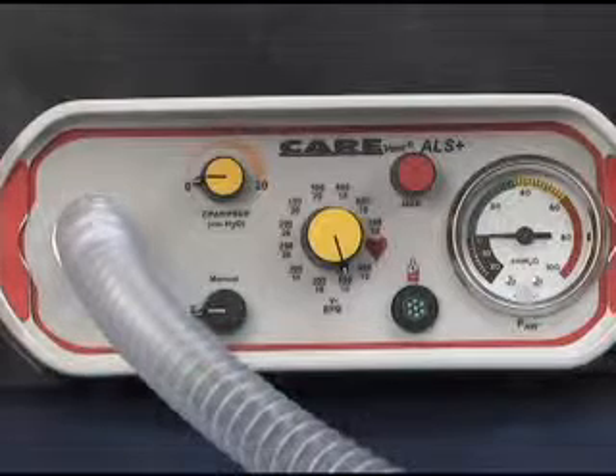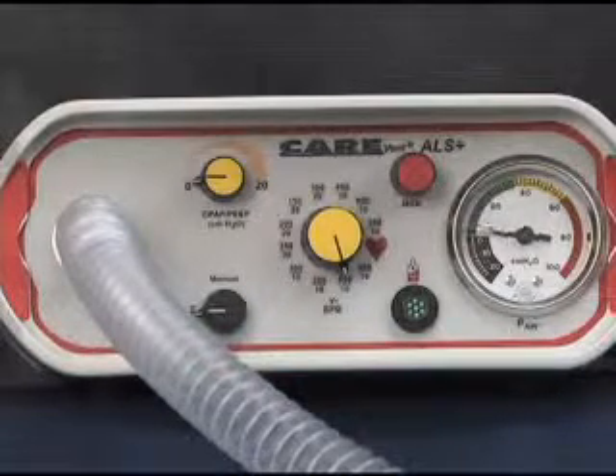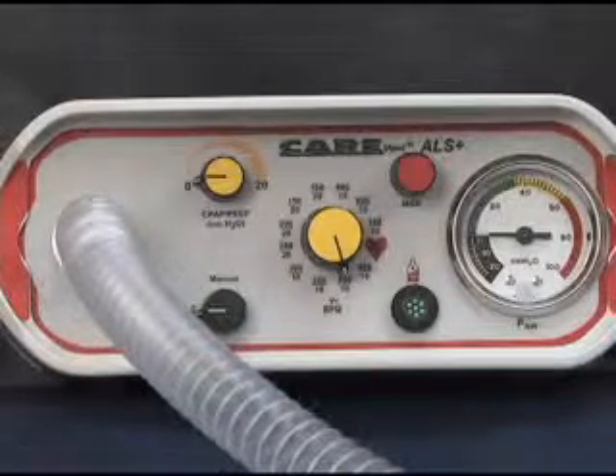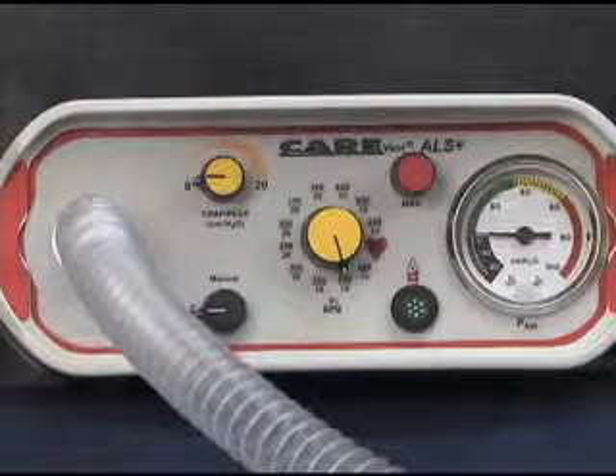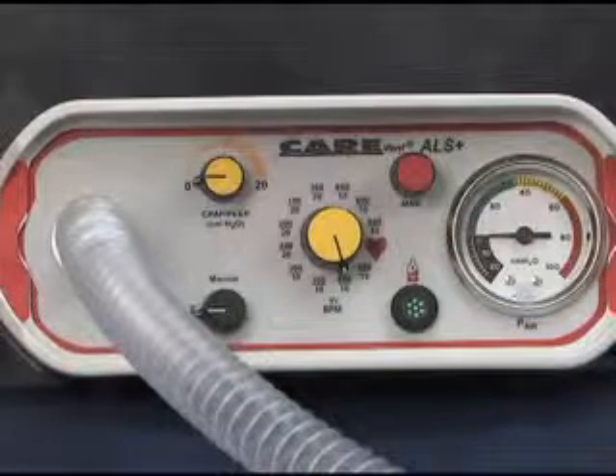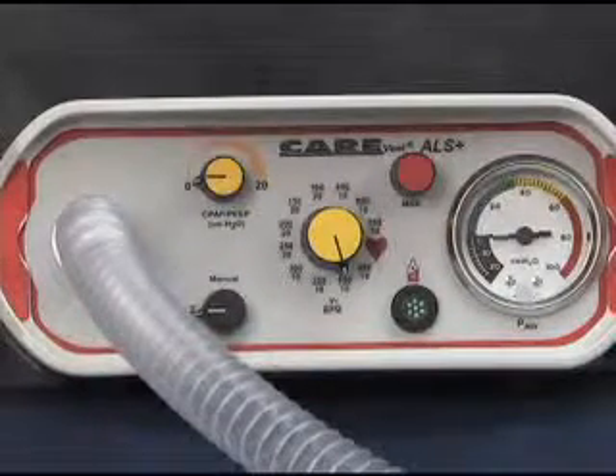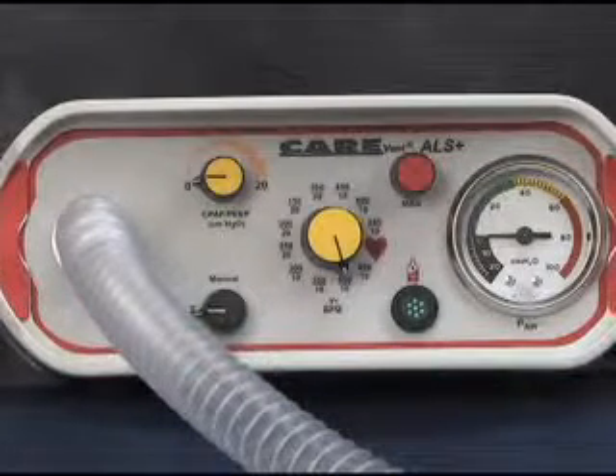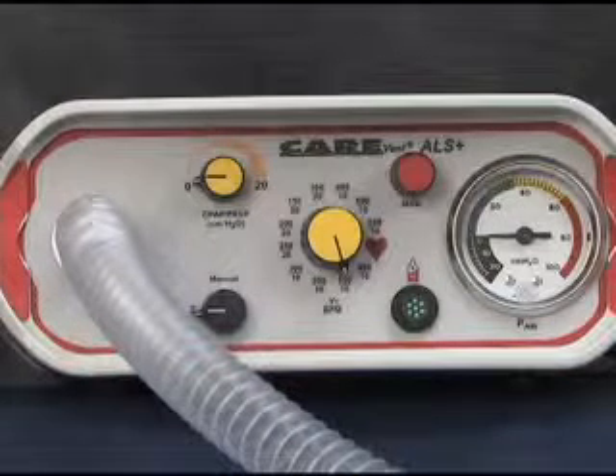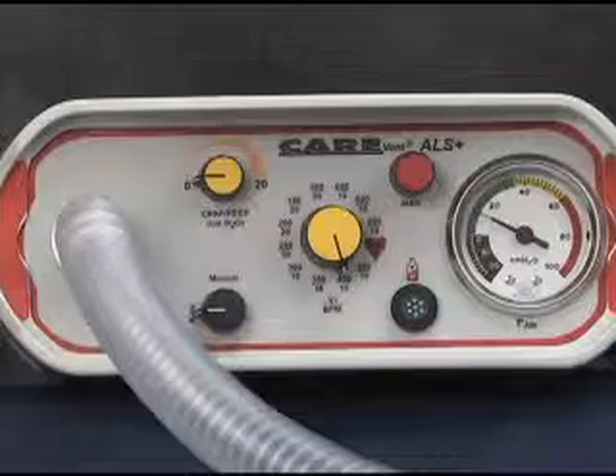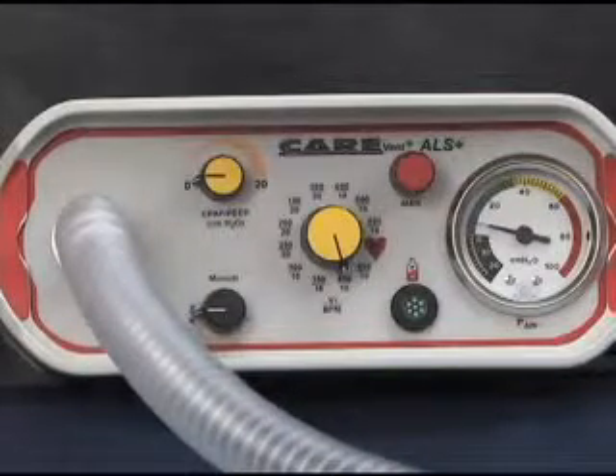In the automatic mode, should the patient commence breathing spontaneously, the CAREvent ALS Plus or ALS Plus CPAP ventilators will sense the patient's inspiratory effort, and the auto shutoff circuit will stop the automatic cycling of the ventilator if the patient's spontaneous flow rate exceeds 30 liters per minute for greater than 1 second. This allows the patient to demand breathe at up to 120 liters per minute on 100% oxygen at their own rate and volume. In order to initiate demand flow in the mask-ventilated patient, the operator must obtain a positive mask-to-face seal. The automatic cycling will restart if the patient's demand flow drops below 30 liters per minute for greater than 4 seconds. This takes place without any intervention on the part of the operator. Automatic cycling restarts will typically take between 4 and 7 seconds, depending on the depth of the patient's respirations.